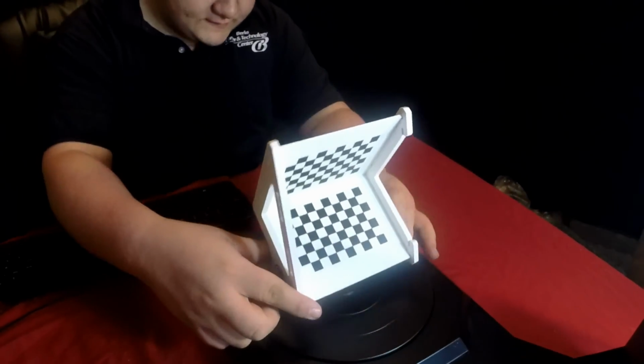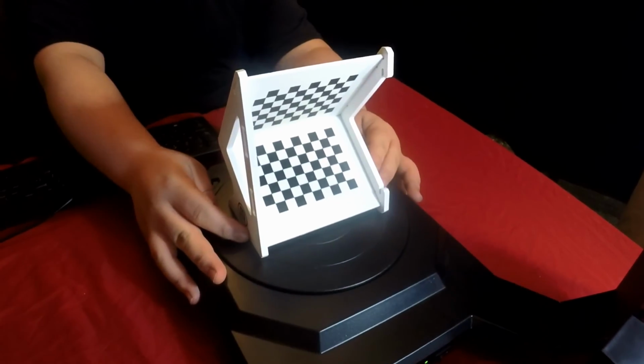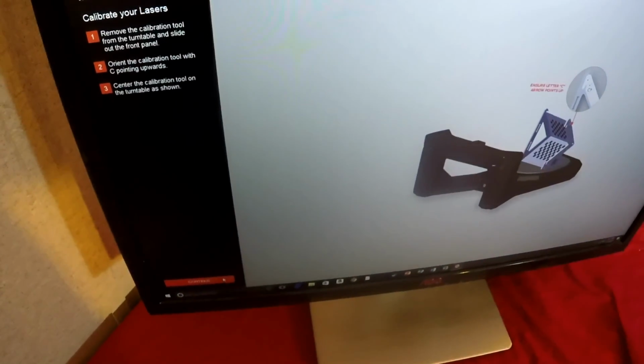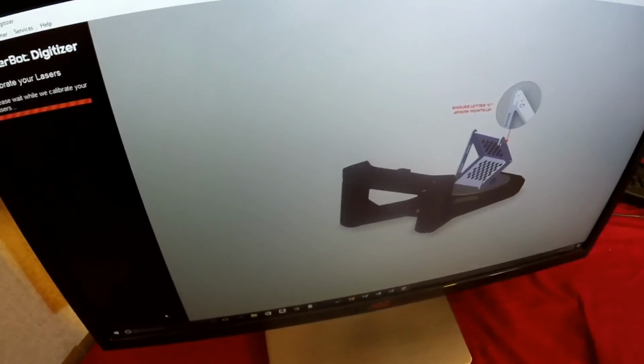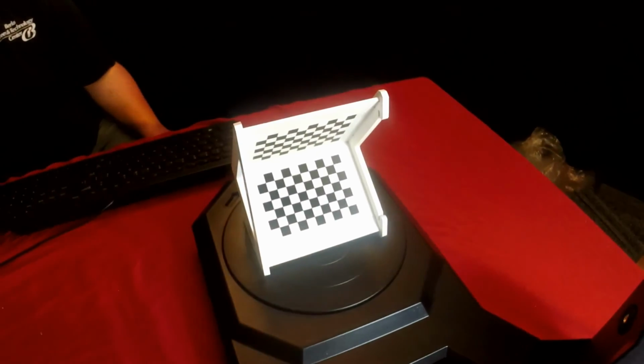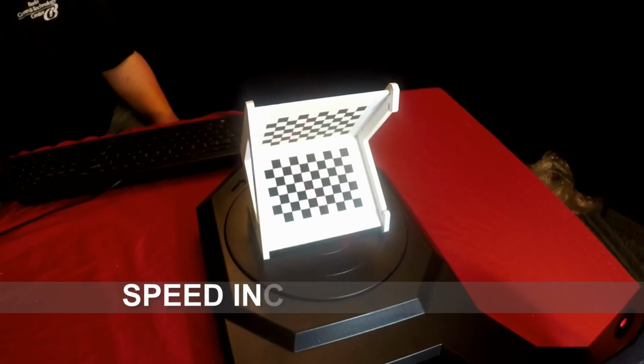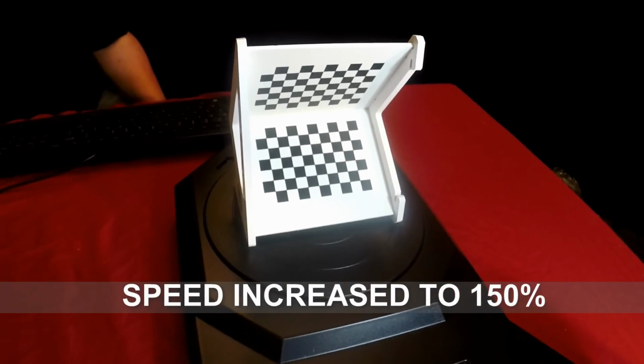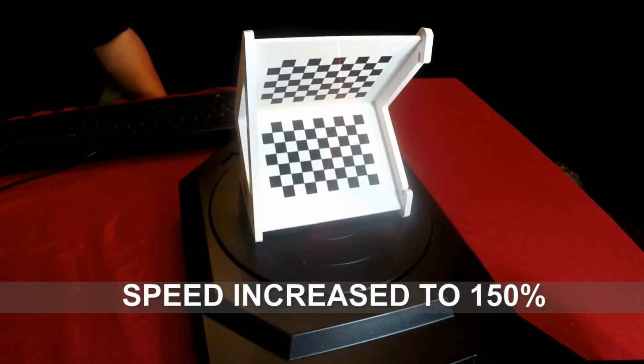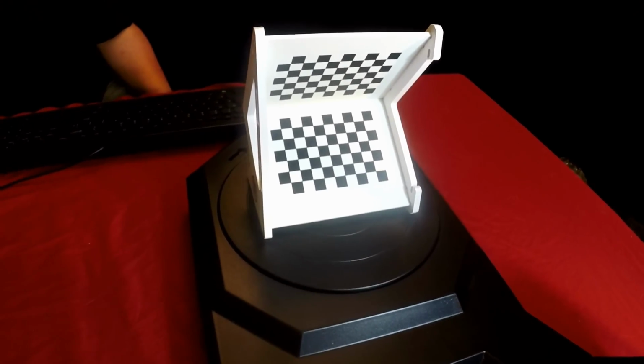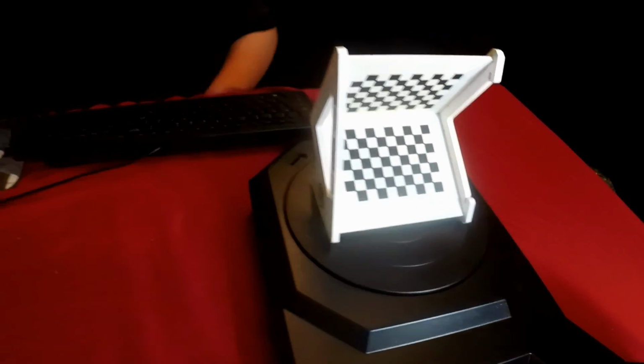There is no little knob on either side, so you just kind of make it center the best that you can. Then you'll come over and you'll click continue and the lasers will come on. You might not be able to see the lasers on camera, but it'll go through the one side and then it will go to the other side. Calibration complete. So you click continue, and then it puts you back at your main screen, and you can take this off, and then you're ready to start scanning.